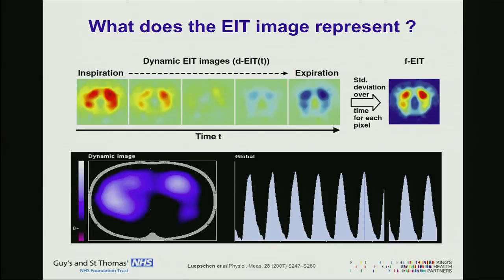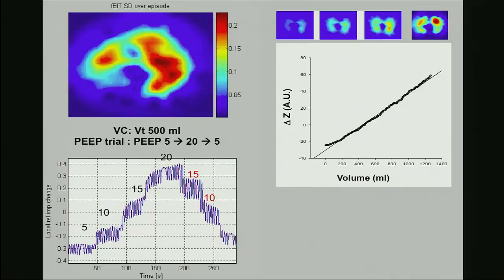The changes in impedance in EIT are linearly related to tidal volumes or volume changes. We can calculate two clinically relevant changes in volume. One is the change in impedance due to tidal ventilation, corresponding to the changes in volume for each breath — compressed over time — which corresponds to tidal volume. These are called tidal variations, because we can't precisely assign a volume for a region of the lung with this technique. We can also find out end expiratory lung volume.